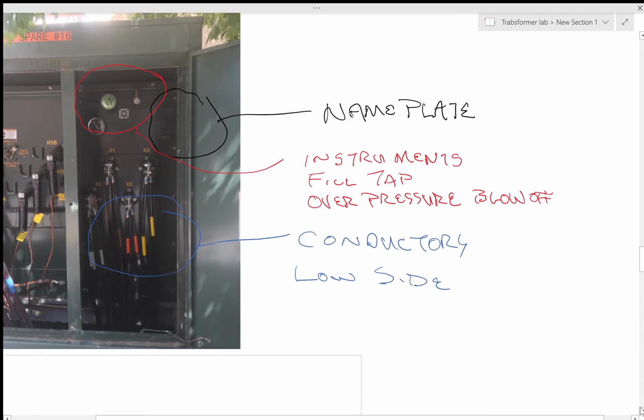Okay, so here's the low side of the transformer. And typically the nameplate will usually be somewhere in this corner. You've got all the instruments and the fill valve over here, the pop-off valve. If anybody knows anything about a hot water heater, you've got a pressure release valve in there. Well, you've got one on a transformer. It can get too hot. Also, down here at the bottom, there's a sample oil valve.